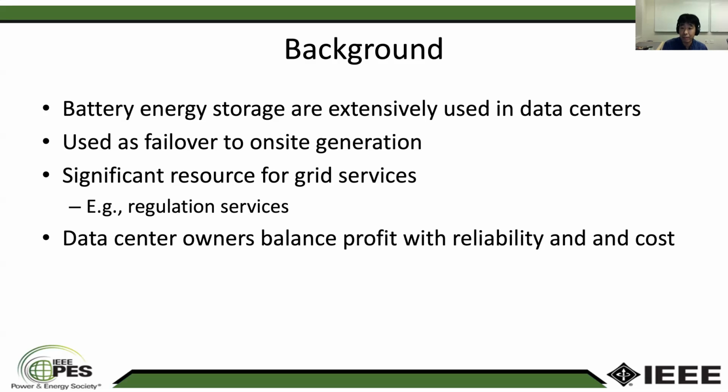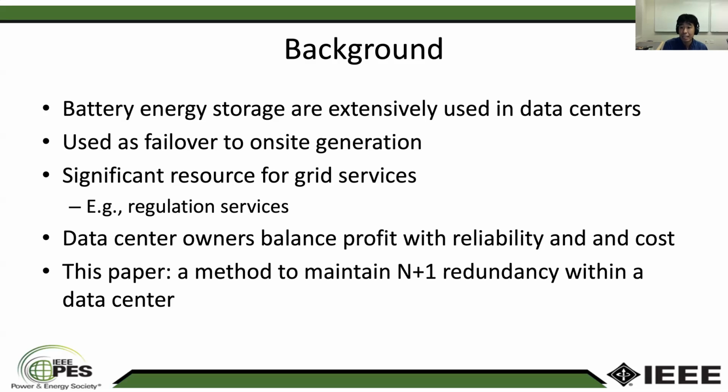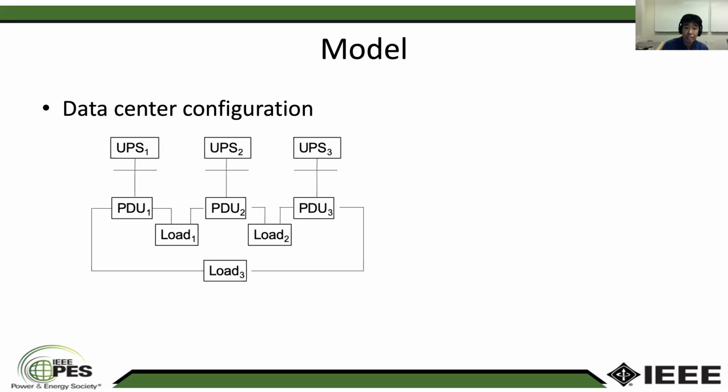In this paper, being backup in the data center is not as simple as just having the total energy available. We will look at a case where the batteries inside the data centers have to maintain the so-called N+1 redundancy. And subject to this constraint, how do we use them for grid services?